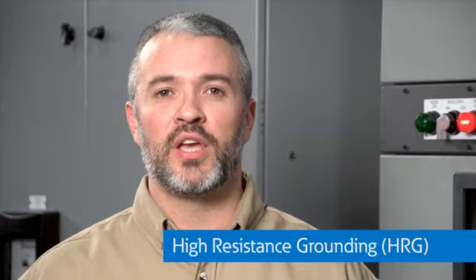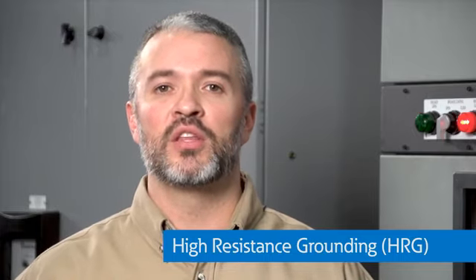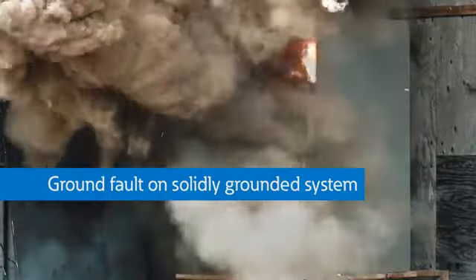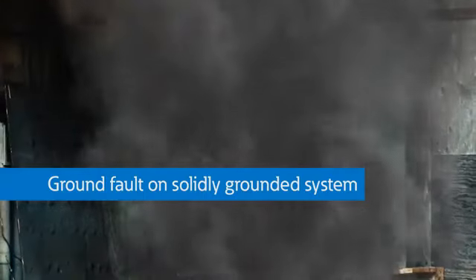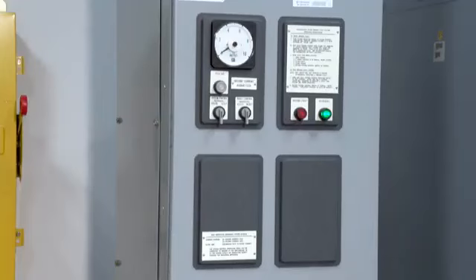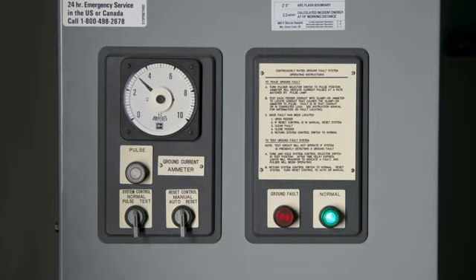This results in improved personal protection and prolonged equipment life. Typically, when a fault occurs on a solidly grounded power system, tens of thousands of amps of fault current flow to the fault. A high-resistance grounding, or HRG system, limits the magnitude of current during a phase-to-ground fault to less than 5 amps. This reduces arc flash energy, increasing personnel and equipment protection.